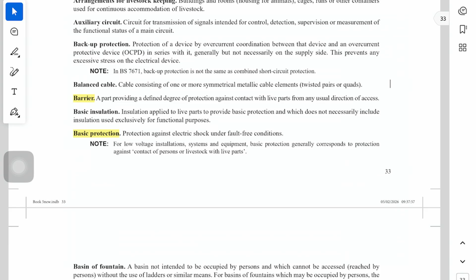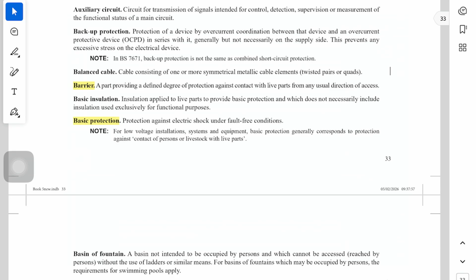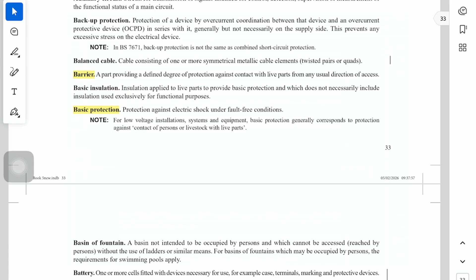Going down to basic protection, this is your insulation, barriers or enclosures, and other bits and pieces. This is protection against electric shock under fault-free conditions. Don't worry about the wording, all you need is to be familiar with it. So when you come to reading the question, it might say what protection would be used to protect against electric shock under fault-free conditions - basic protection, fault protection, whatever. You need to map it back.